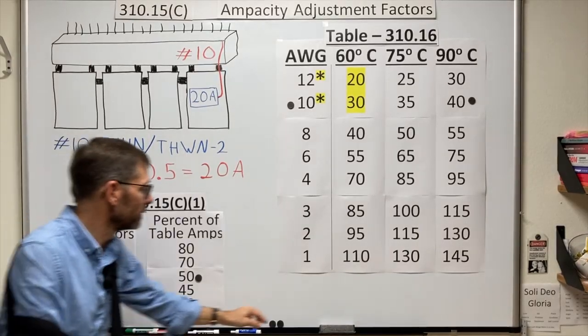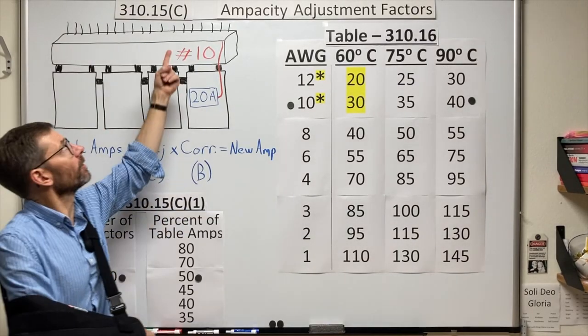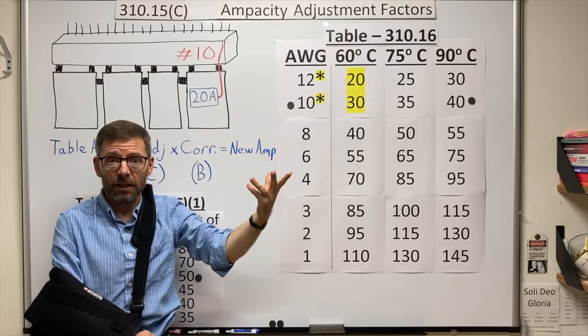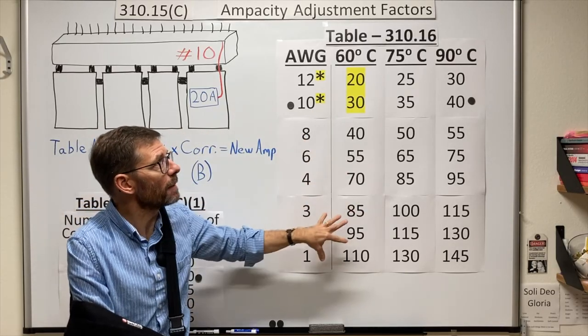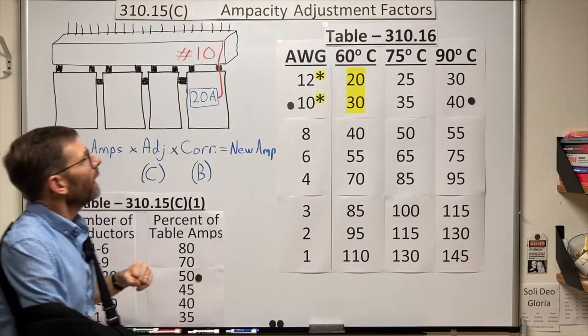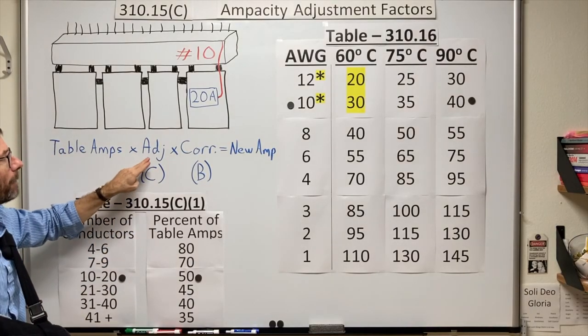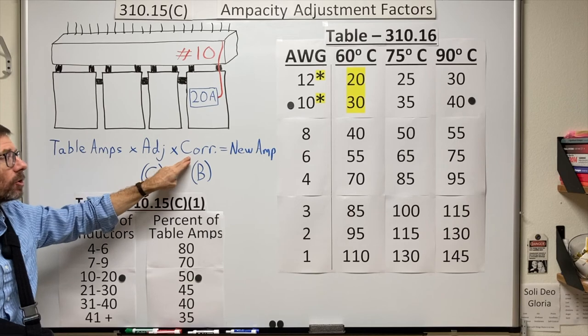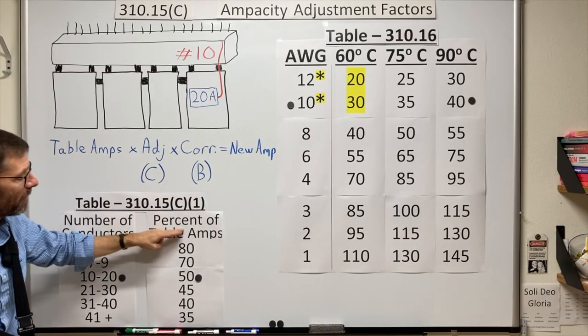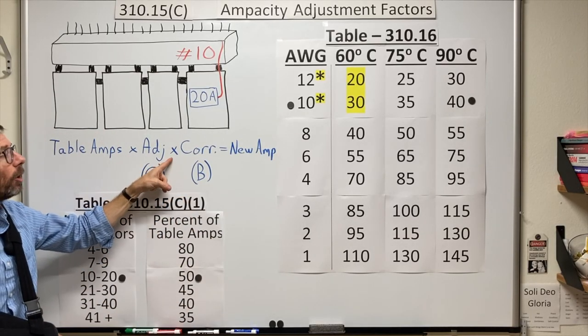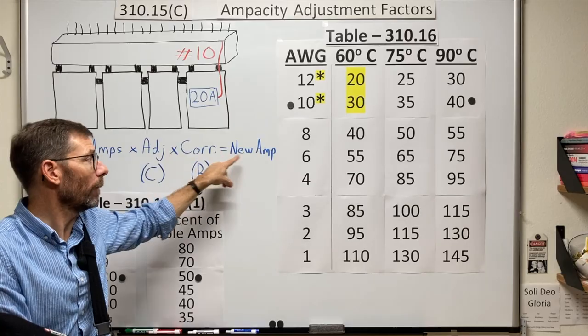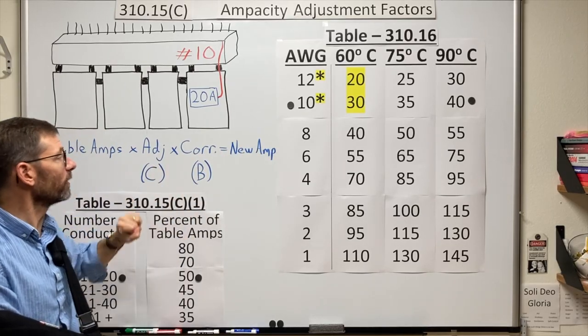One final comment I want to make here. This video has been about 310.15(C) ampacity adjustment. But if we look at B, that's another video, it's on temperature correction. How do we adjust these amps if the ambient temperature is different than that that the table is rated for? And if we need to do both of these, ampacity adjustment from C, and correction from B, the process would be take my table amps, multiply by my factor for the adjustment, and then multiply again by the factor from the tables for temperature correction. And that would equal the new amps. So if you have to employ both of them, that's the process.